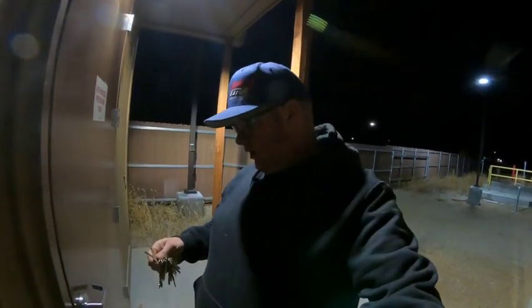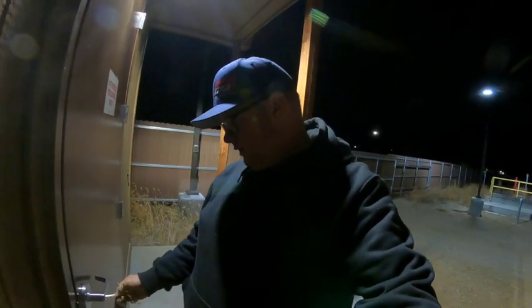Well, hello, it's 11 o'clock and I'm out here at River Run. Got an alarm, high level alarm. We're gonna see what it is. Sounds like the pump's running, but the pump's not pumping. Yep, I can hear the VFD running.